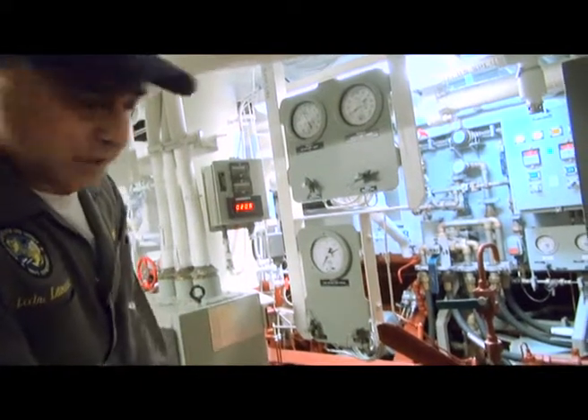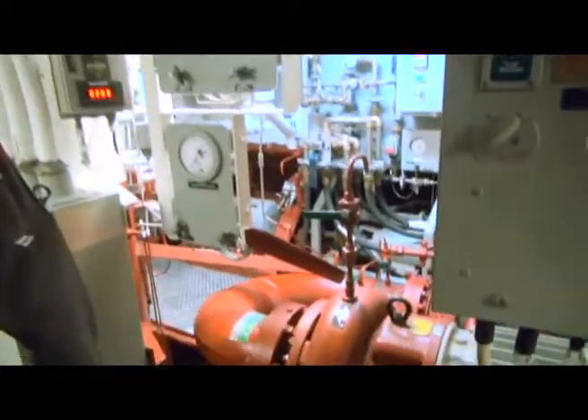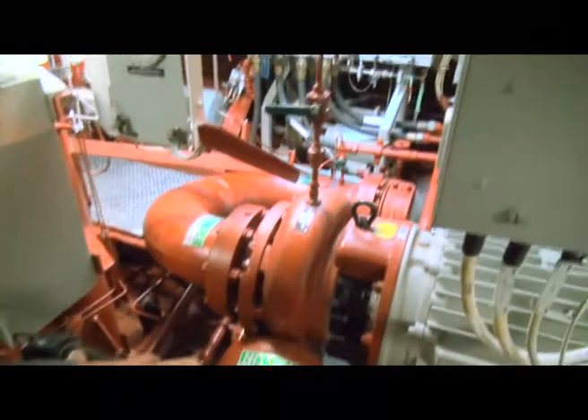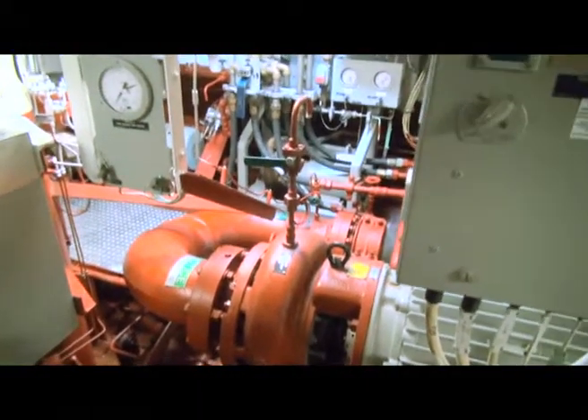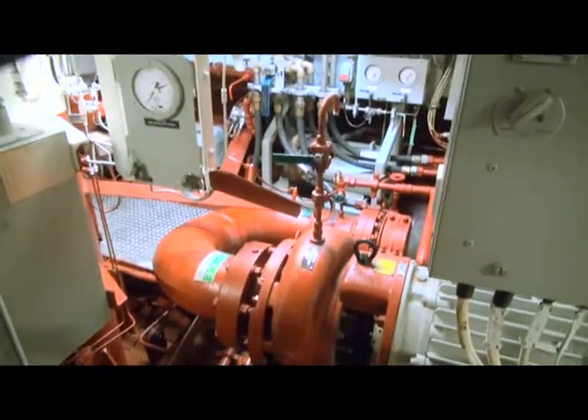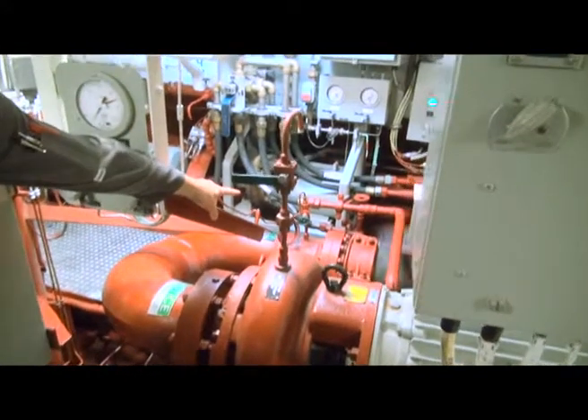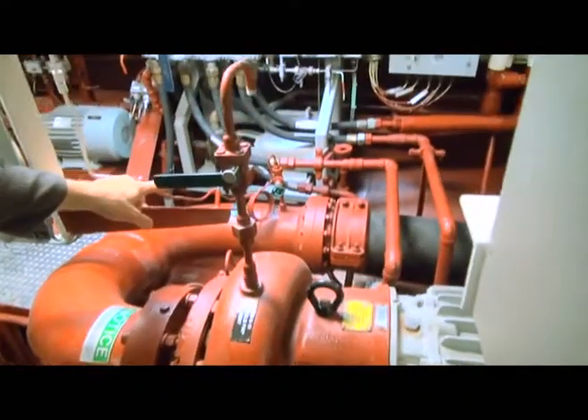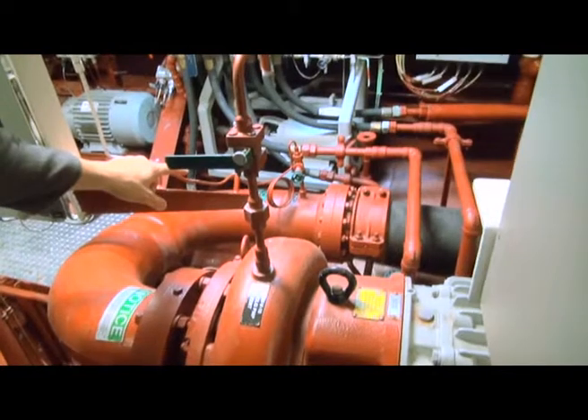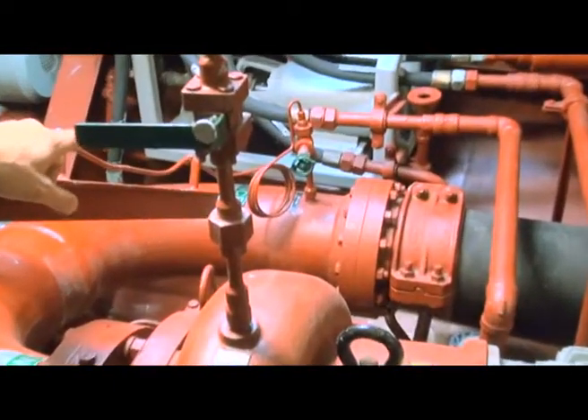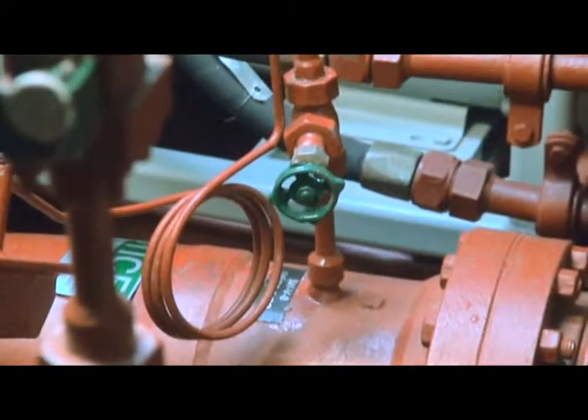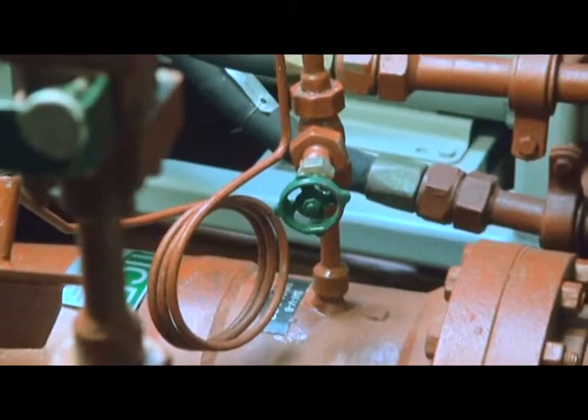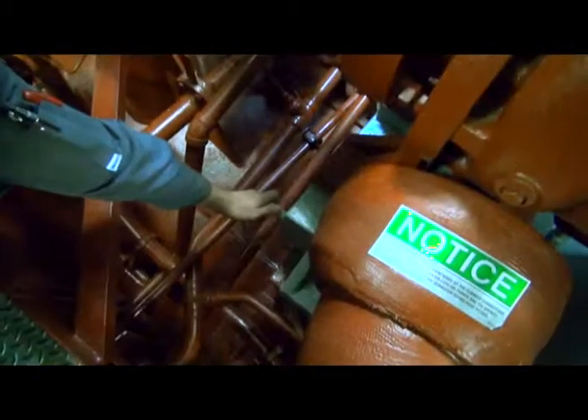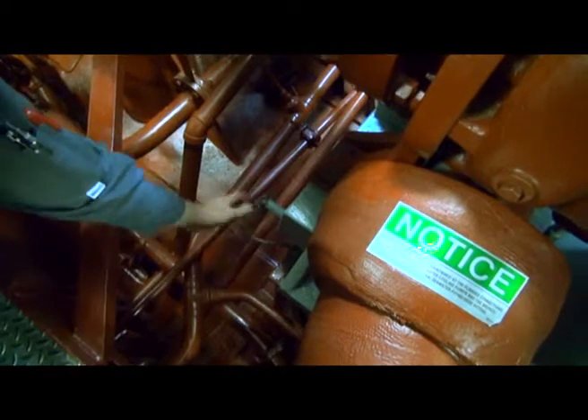And then the other thing I like to do is check the root valves too, because the root valves are similar to the isolation valves. They don't get a lot of love, and from time to time we find those seized. So, like this one, I would shut it down a couple turns and then open it a couple turns, just to make sure that the valve's not seized. We find a lot of those seized, especially on the older ships. Make sure that the grounding straps are intact and that they're tight.